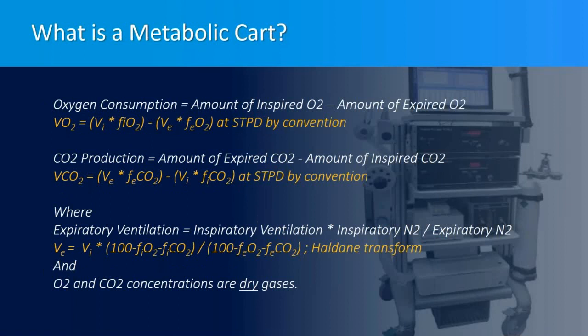To calculate oxygen consumption, subtract the amount of expired oxygen from the amount of inspired oxygen. To calculate CO2 production, subtract the amount of inspired CO2 from the amount of expired carbon dioxide. The O2 and CO2 concentrations are assumed to be dry gases. Expiratory ventilation may be determined from inspiratory ventilation using the Haldane transform. O2 consumption and CO2 production are determined by either direct application of these equations or a combination of equations and proprietary algorithms. It is important to note that VO2 and VCO2 are derived values, not measured values.